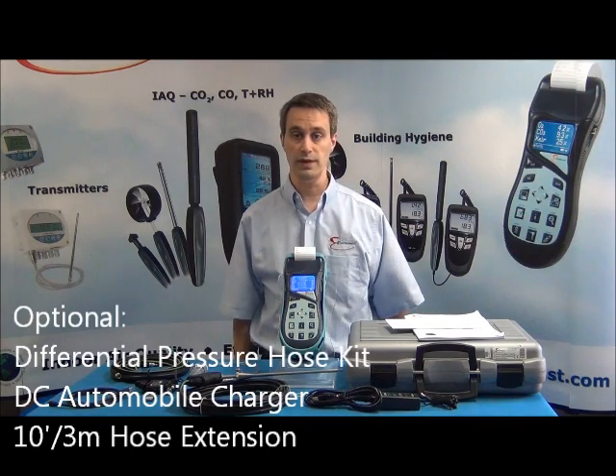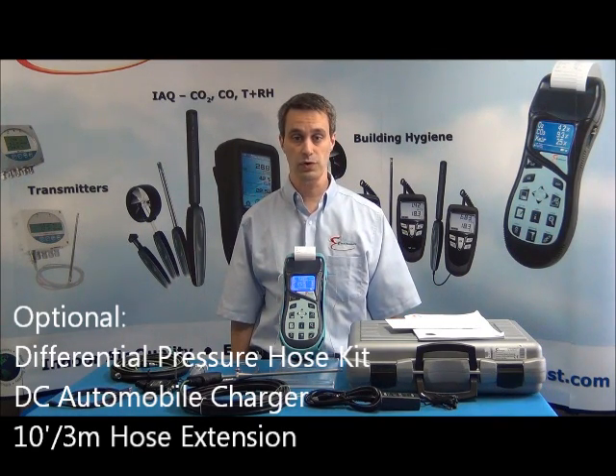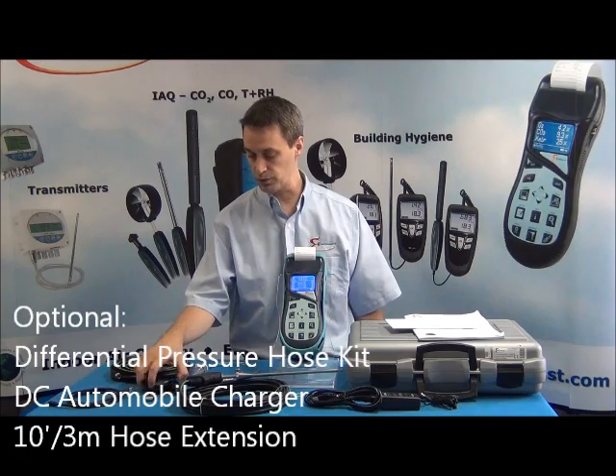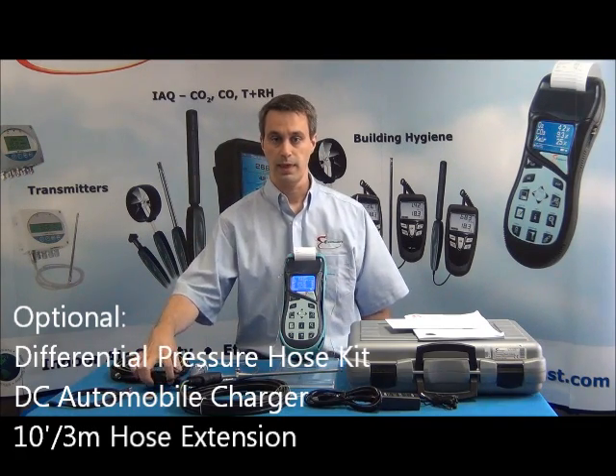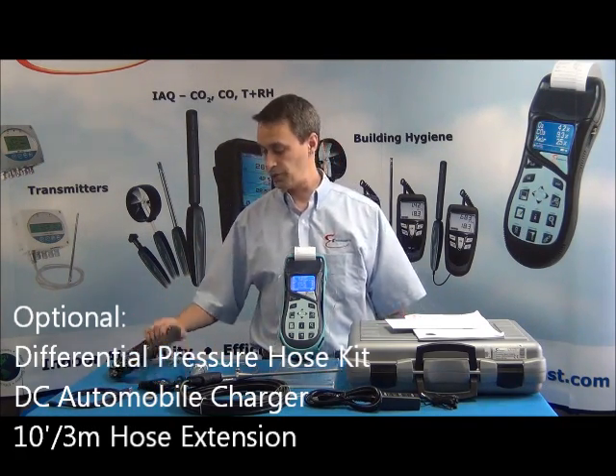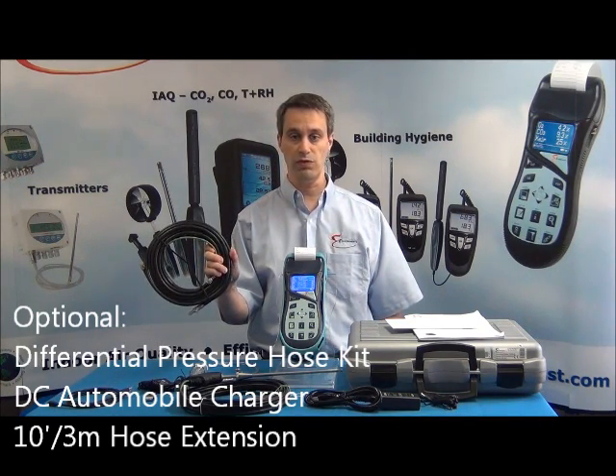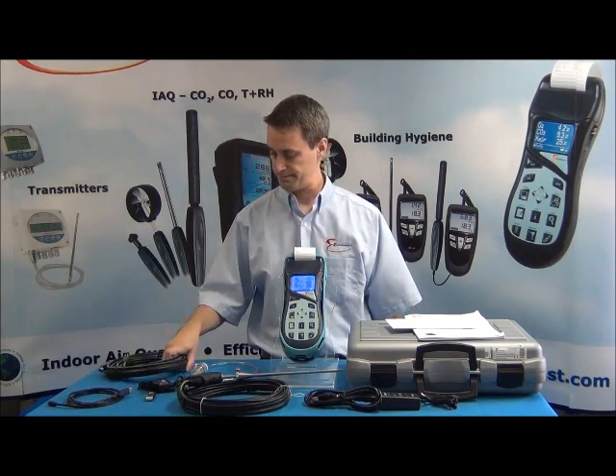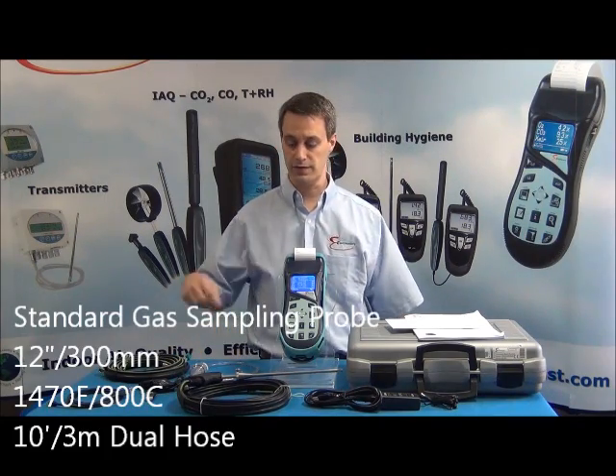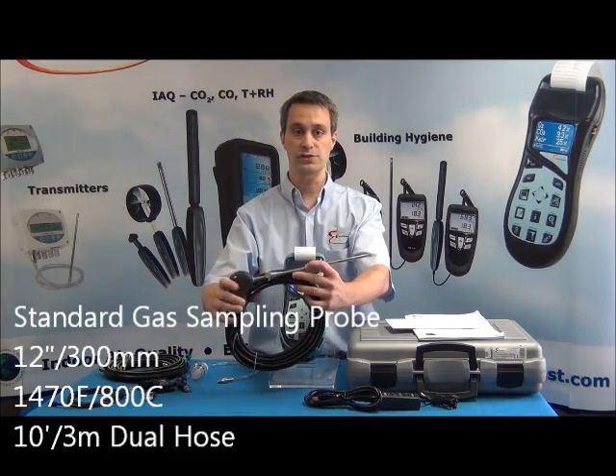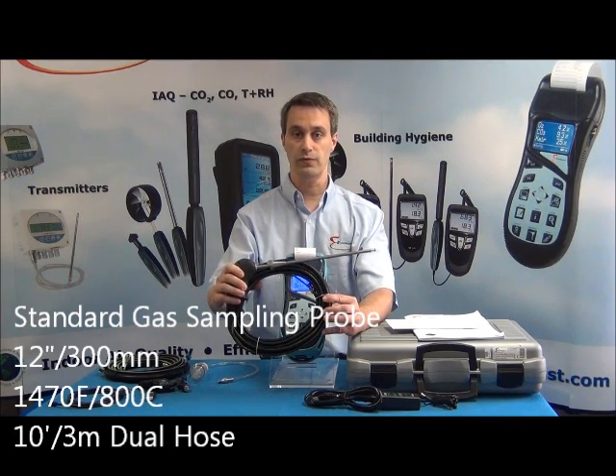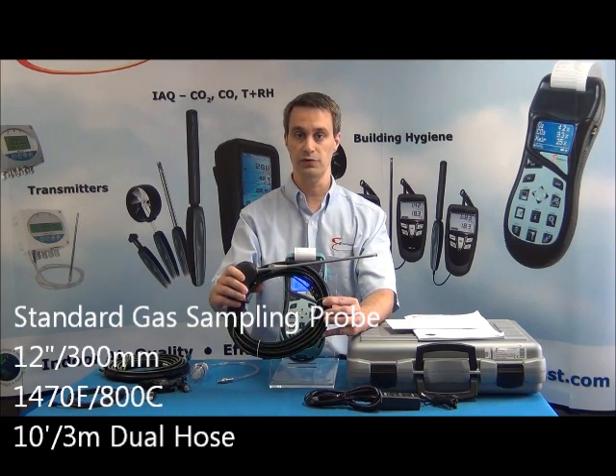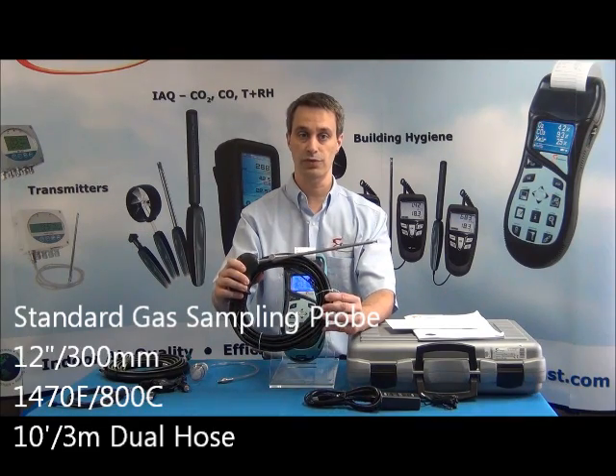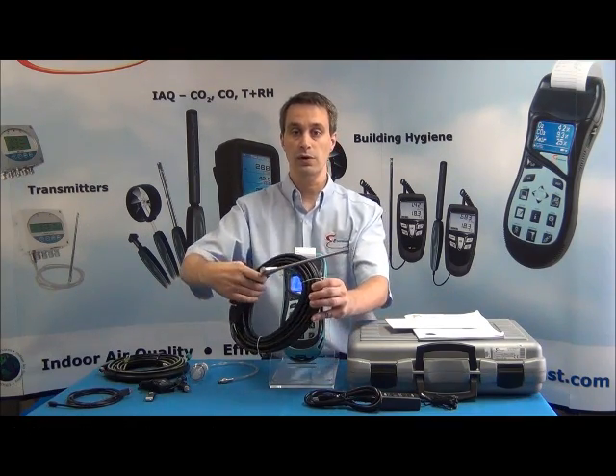Optional items that can be used with the E4400 include a differential pressure hose kit, a DC automobile charger, and a 10-foot, 3-meter hose extension for use with tall or hard-to-reach stacks. The standard gas sampling probe is 12 inches, 300 millimeters long, good up to 1470 degrees F, 800 degrees C, and includes 10-foot, 3-meter dual hose. Longer and higher temperature probes and hose extensions are also available with the E4400.